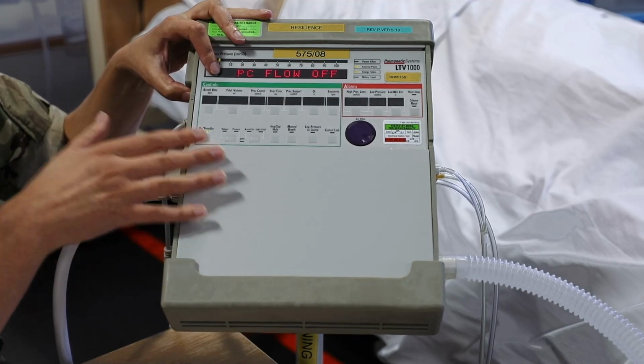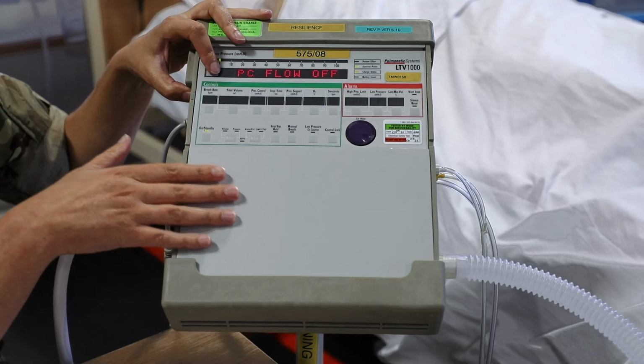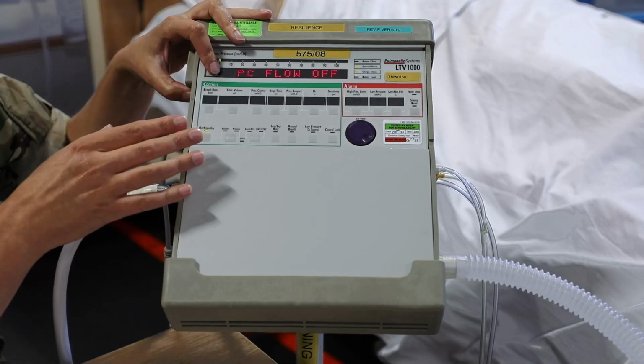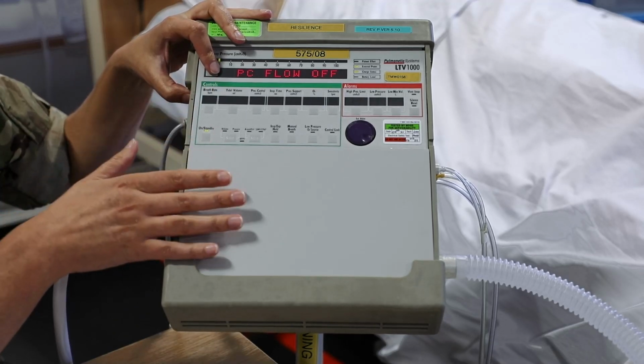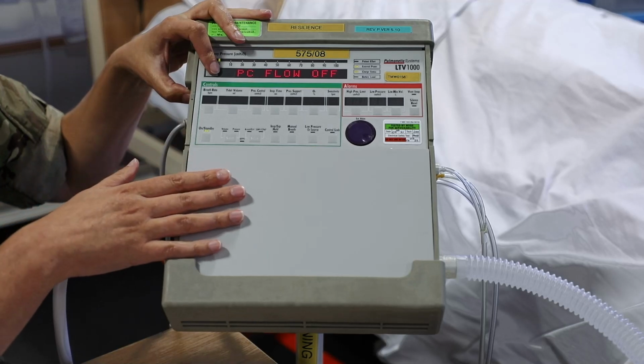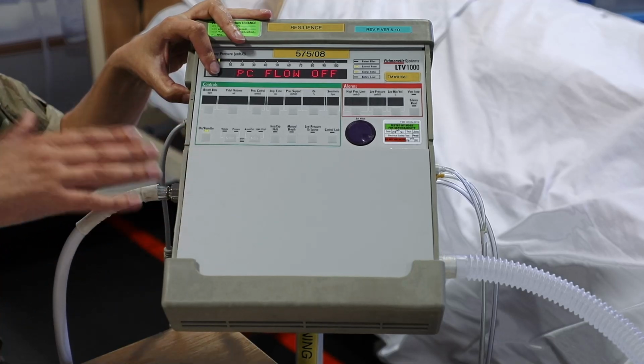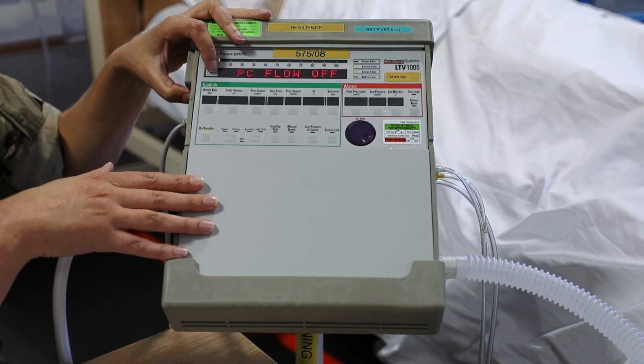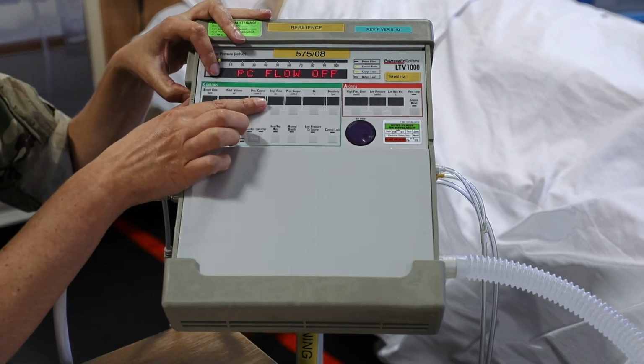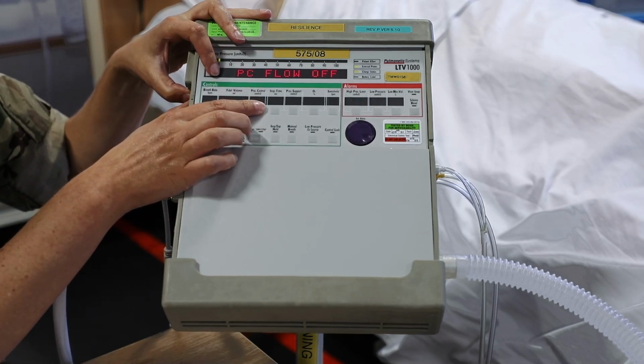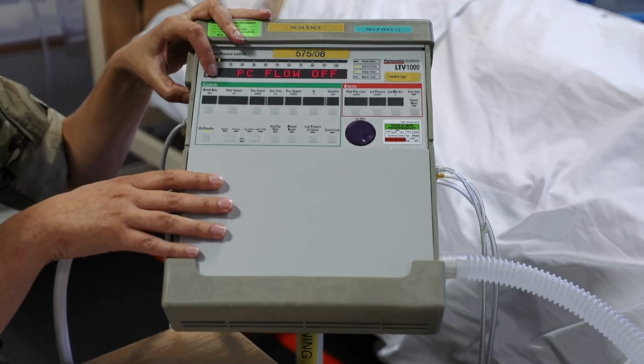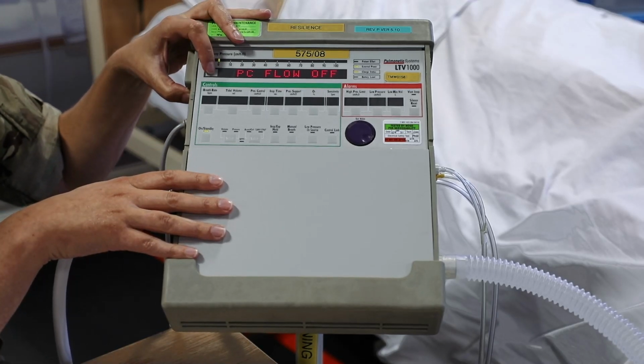As standard, we would have it switched off in the menu because it doesn't seem to have much utility. But obviously, if one of the anaesthetists or intensivists want to select that as a function, then you can have it on, and it will try and mirror the flow of the spontaneous breaths. So we prefer to have it off and just rely on the inspiratory time and the respiratory rate for cycling, but there is an option in there for pressure control flow as well.